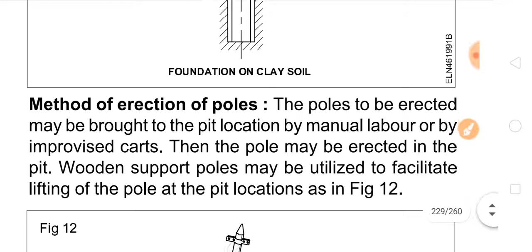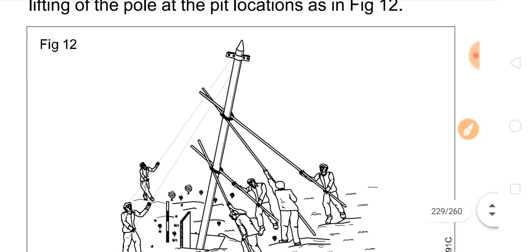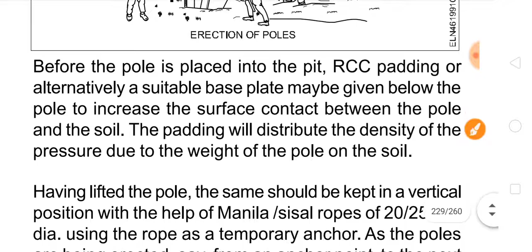Method of erection of pole. The pole to be erected may be brought to the pit location by manual labor or by improvised carts. Then the pole may be erected in the pit. Wooden support poles may be utilized to facilitate lifting of the pole at the pit location, as in picture 12, which shows the erection of poles. Before the pole is placed into the pit, RCC padding or alternatively a suitable base plate may be given below the pole to increase the surface contact between the pole and the soil. The padding will distribute the density of the pressure due to the weight of the pole on the soil.